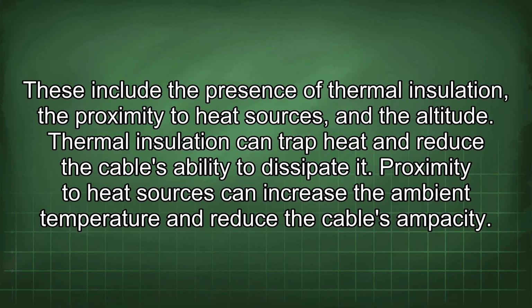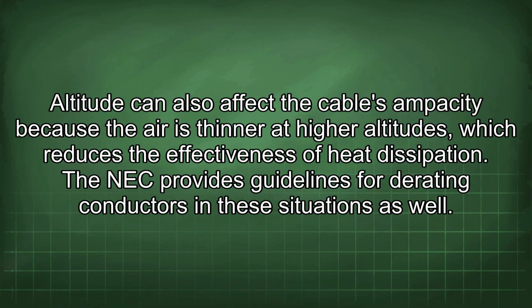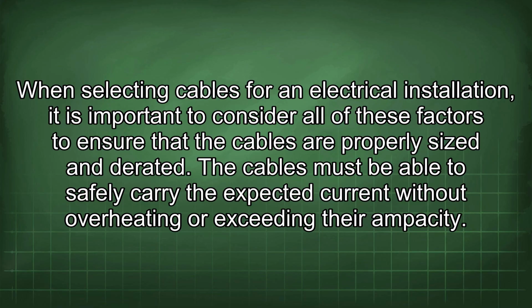These include the presence of thermal insulation, the proximity to heat sources, and the altitude. Thermal insulation can trap heat and reduce the cable's ability to dissipate it. Proximity to heat sources can increase the ambient temperature and reduce the cable's ampacity. Altitude can also affect the cable's ampacity because the air is thinner at high altitudes, which reduces the effectiveness of heat dissipation. The NEC provides guidelines for derating conductors in these situations as well. When selecting cables for an electrical installation, it is important to consider all of these factors to ensure that the cables are properly sized and derated.